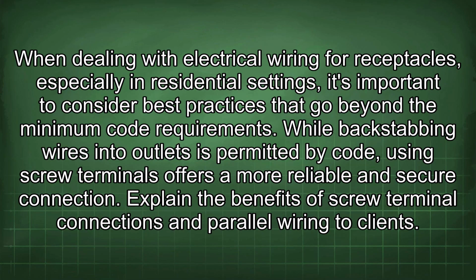When dealing with electrical wiring for receptacles, especially in residential settings, it's important to consider best practices that go beyond the minimum code requirements. While backstabbing wires into outlets is permitted by code, using screw terminals offers a more reliable and secure connection. Explain the benefits of screw terminal connections and parallel wiring to clients.